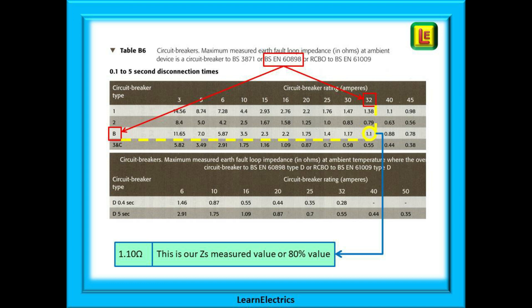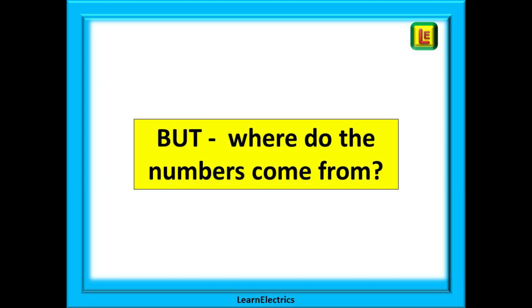What else does the table tell us? At the top it tells us it is a maximum measured value — in other words, after measuring the actual ZS with your meter you can make a direct comparison to the tables. This figure has already been adjusted for voltage fluctuations and temperature variations, as we shall see in just a moment. If the reading on your meter is less than the values shown on the chart then that is an acceptable reading. But where do these numbers come from? They are not just plucked out of the air, so let's start from the beginning.